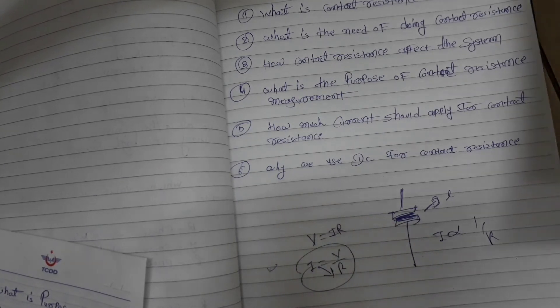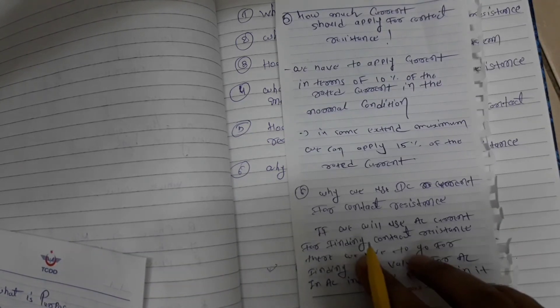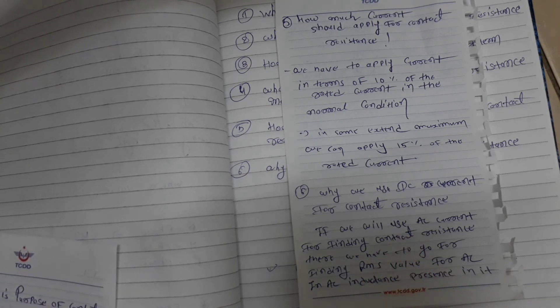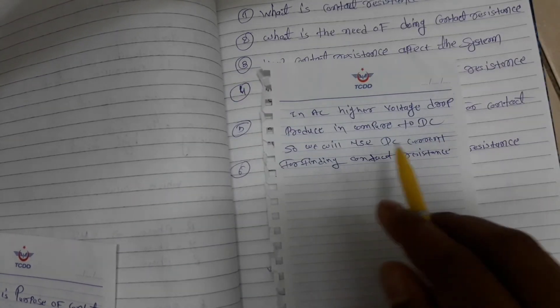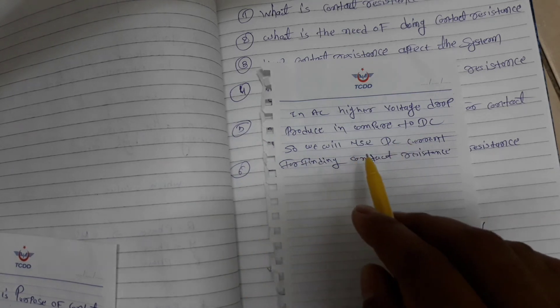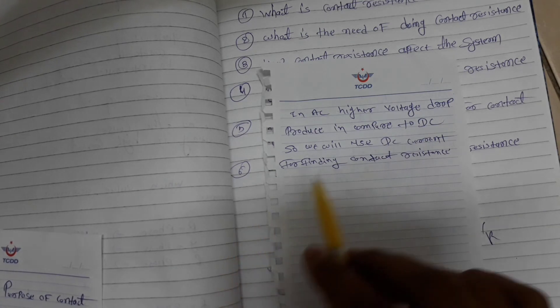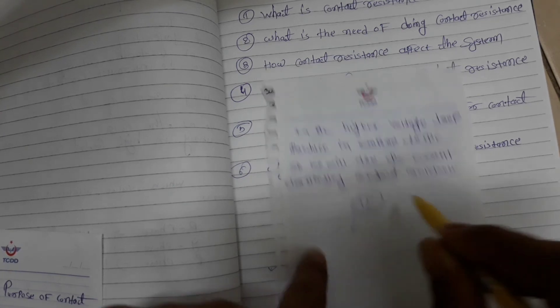Why do we use DC current for contact resistance measurement, and not AC? The answer is: if we use AC current, we have to find the RMS value, and AC has inductance present. In AC, a higher voltage drop is produced compared to DC. So we use DC current for contact resistance measurement — when we perform contact resistance measurement, we inject DC current.